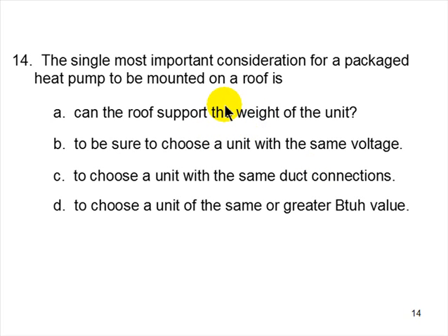Maybe that unit never ran. That part of the building was never occupied, and it had no moving load. The result is, and the answer should be obvious, it had no vibration, so it had no real load attached to it. Now you come in, you get rid of that thing because it sat there for 5 years in an unoccupied building. You put a new one on, you start it up, it starts to move and shake and vibrate. There goes the roof because you didn't take a look at the roof.